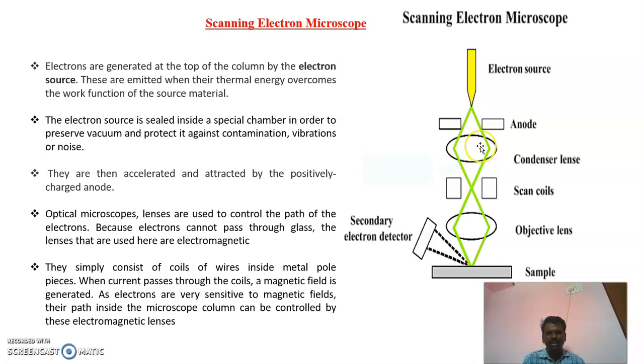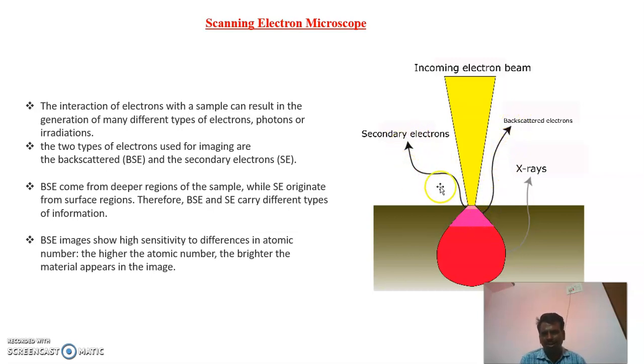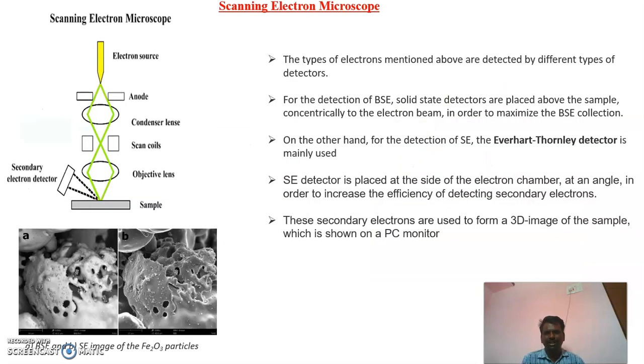After focusing, the electron beam strikes the sample. After striking, two different kinds of electrons are scattered: one is backscattered electrons, and another is secondary electrons. These backscattered electrons originate from the depth of the sample, and the secondary electrons originate from the surface of the sample. Both types are detected by their respective detectors.